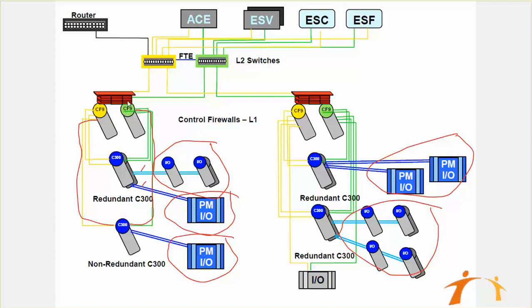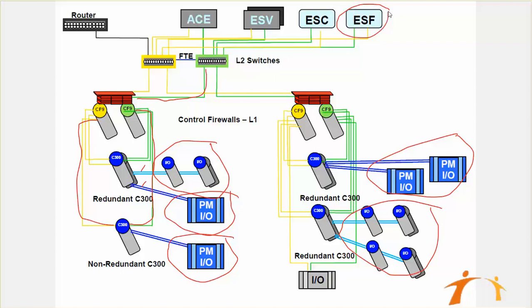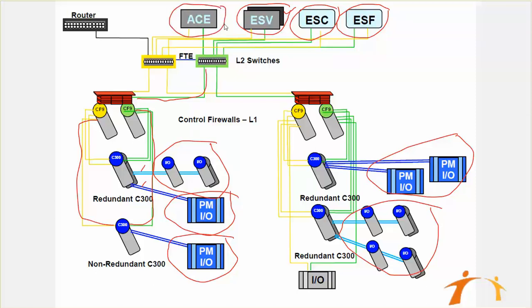After that firewall, the firewall module is connected to uplink FTE Level 2 switches. The primary comes to the primary switch, the secondary comes to the secondary switch. Then you can see that there are various stations shown at the top: ESF stands for Experion FlexStation, ESC is the Experion console station, ESV is the Experion server with redundancy, and ACE is the Application Control Environment, which is your engineering station.